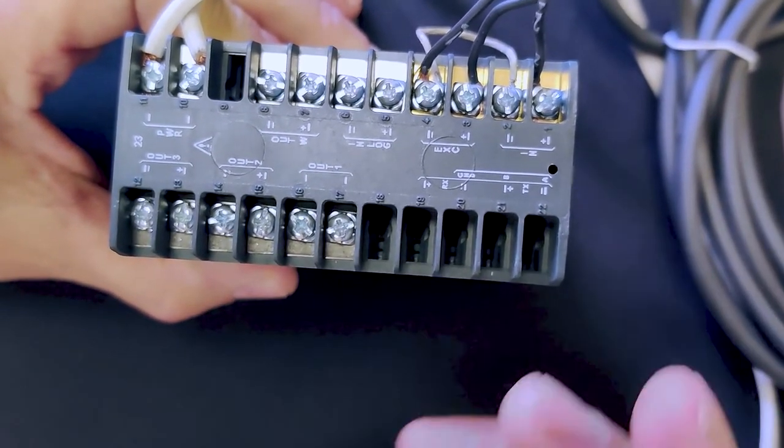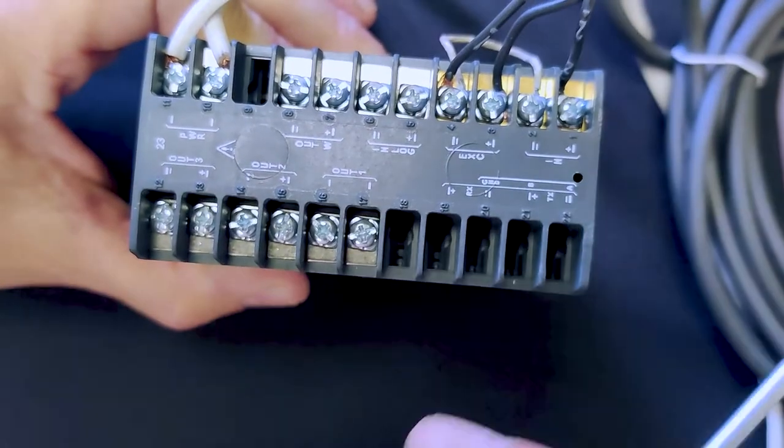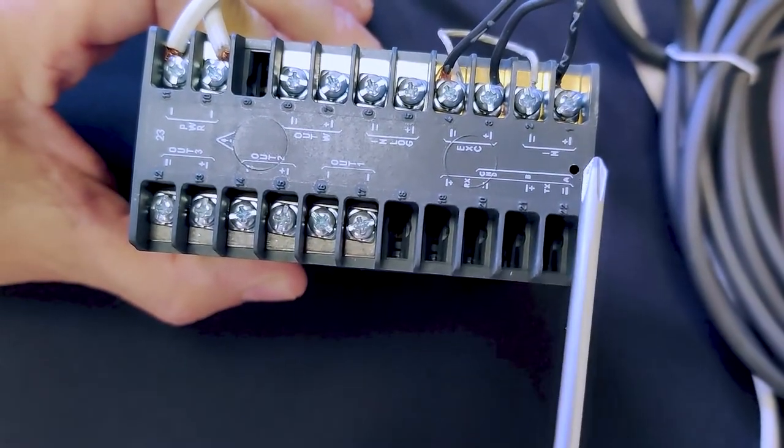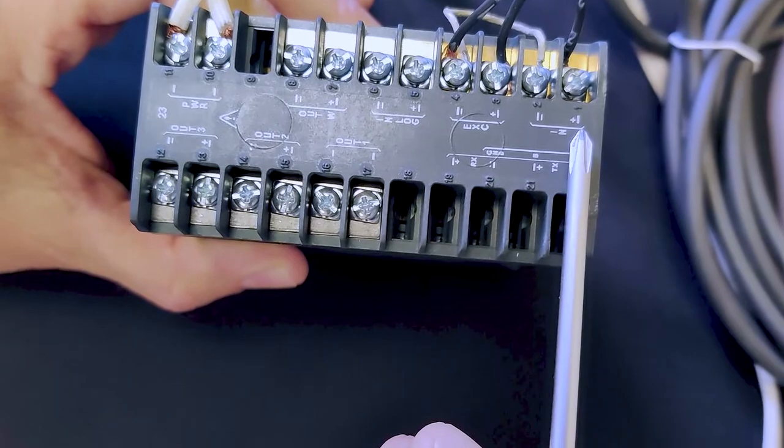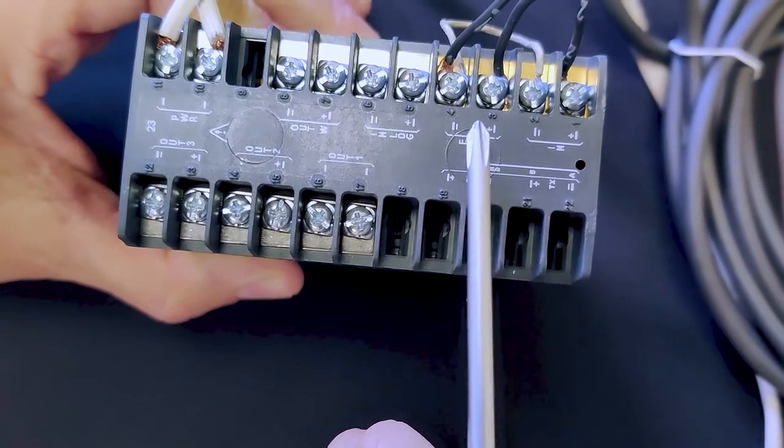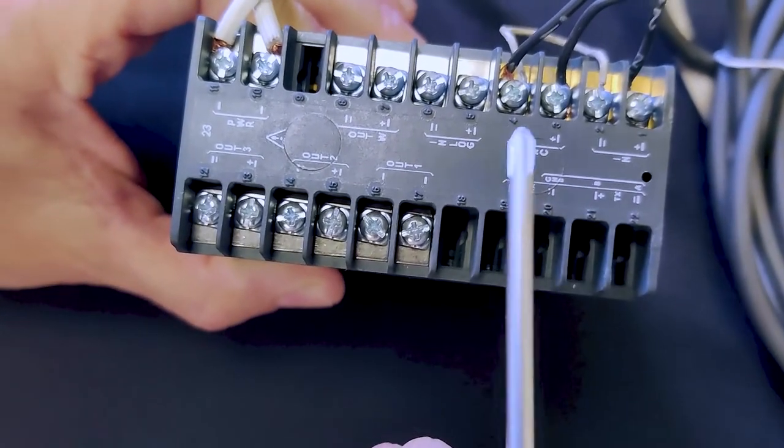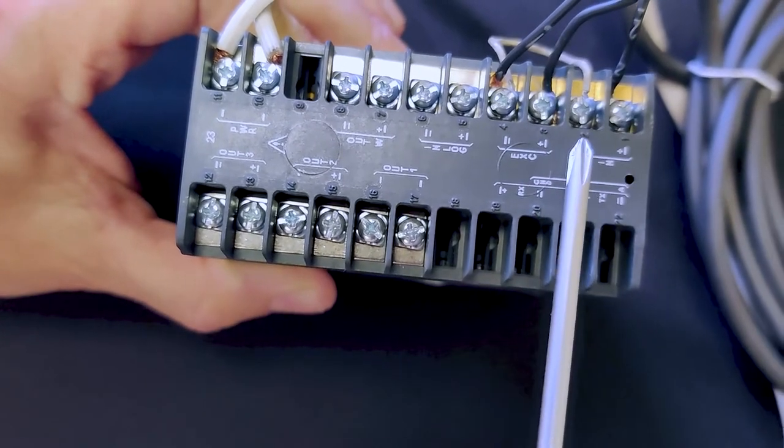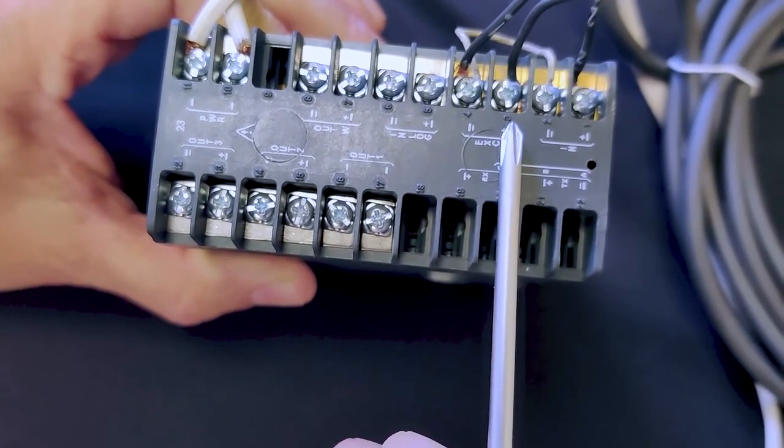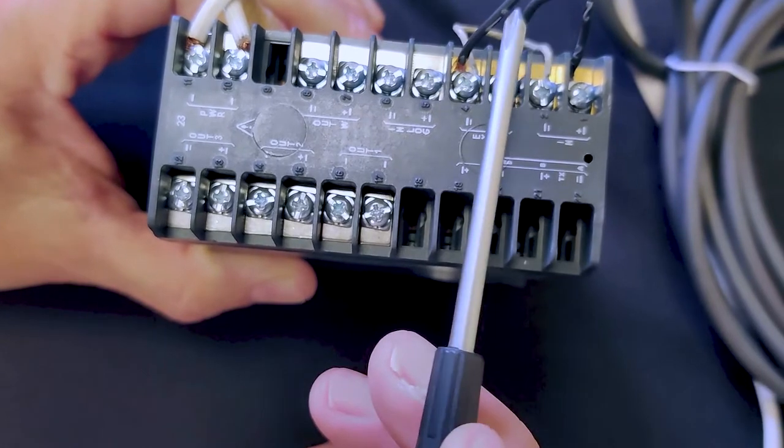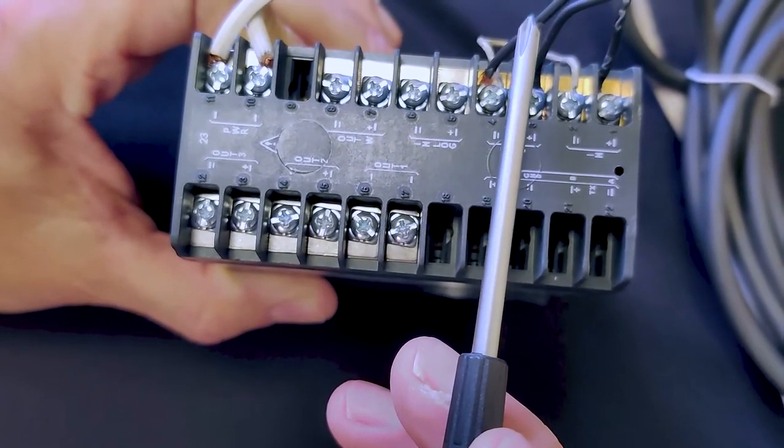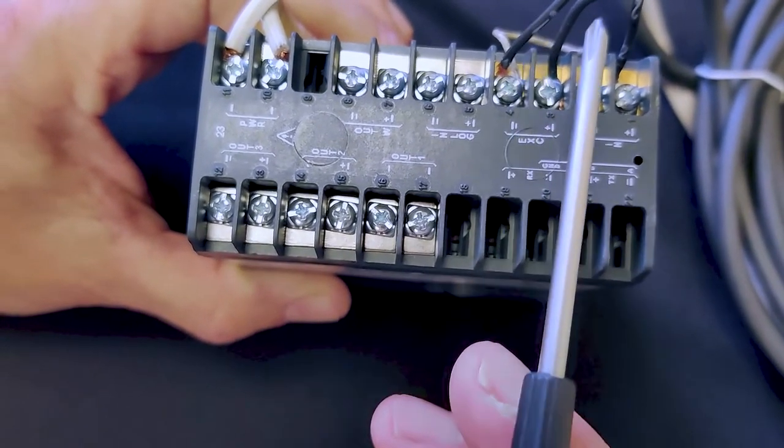The linear pot itself, the wiper, the changing voltage of the pot—this number two wire goes to the positive of the input. The two negatives are jumpered together and you take the other two wires to the excitation voltage. If you reverse these wires it would measure up instead of down or down instead of up.